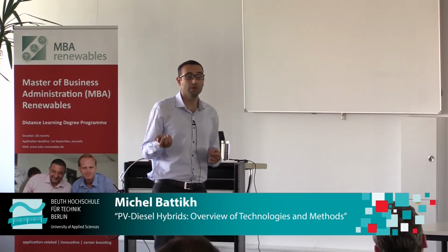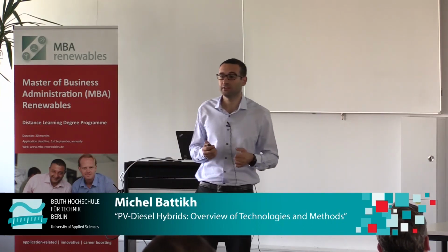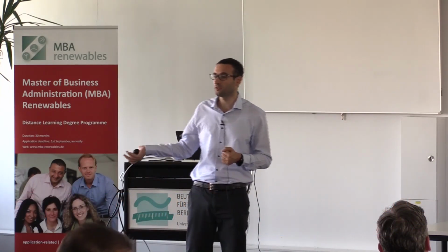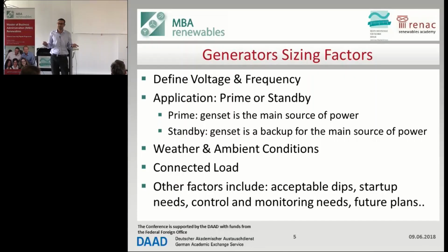We need to know what's the application of our diesel generator. Is it going to be the prime source of energy, or a backup? If it's prime, it should not be as big as if it's a backup. Because if you have a backup, let's say for a hospital, you want to run all the loads on this diesel generator, so it should be able to withstand all the load of the hospital in emergency cases.